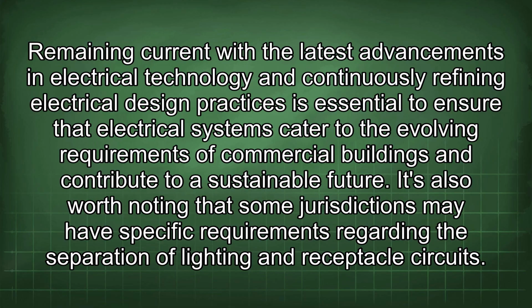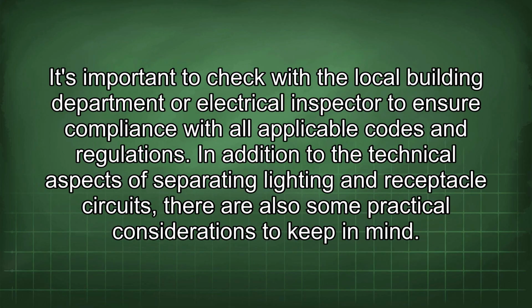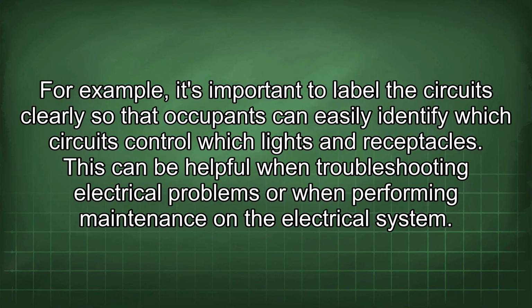It's also worth noting that some jurisdictions may have specific requirements regarding the separation of lighting and receptacle circuits. It's important to check with the local building department or electrical inspector to ensure compliance with all applicable codes and regulations. In addition to the technical aspects of separating lighting and receptacle circuits, there are also some practical considerations to keep in mind. For example, it's important to label the circuits clearly so that occupants can easily identify which circuits control which lights and receptacles. This can be helpful when troubleshooting electrical problems or when performing maintenance on the electrical system.